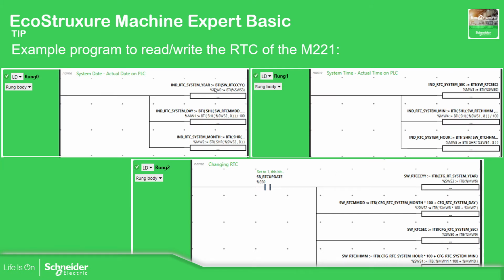So in here, this is a small example of how we can do that without using the function block. In this case, I'm reading the system word %SW52, and I use the operator block SHL to shift 8 bits to the left, so we can separate the day and month in this variable. This is what I usually do, and if I'm not wrong, I have it over here.